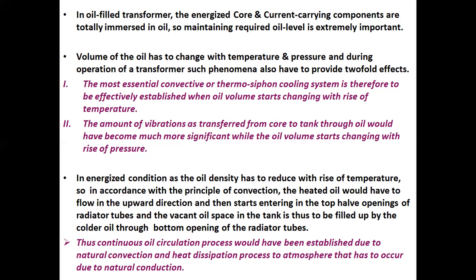One, the most essential convective or thermosiphon cooling system is effectively established when oil volume starts changing with rise of temperature. Number 2, the amount of vibrations transferred from core to tank through oil would become much more significant while the oil volume starts changing with rise of pressure.